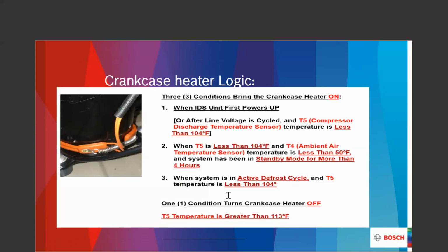A little bit about the crankcase heater. The crankcase heater is nothing more than that device that is plugged into L1 and L2. It is that device that is going to allow the oil to basically start the warming process so that we do not, what the industry calls, slug a compressor. We would like for you to always plug in L1 and L2 as soon as you can upon installing the product, especially in the wintertime. Allow that oil that's in that system to start the process of getting warm so that when we fire this thing up for the very first time, it doesn't have a slugging effect.